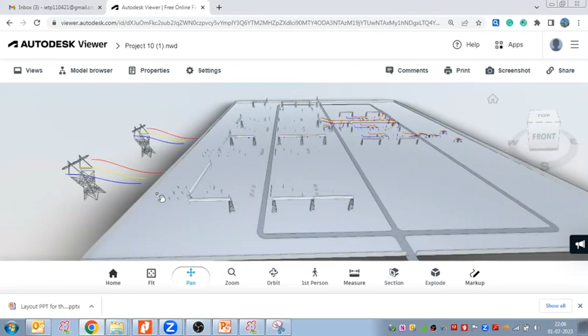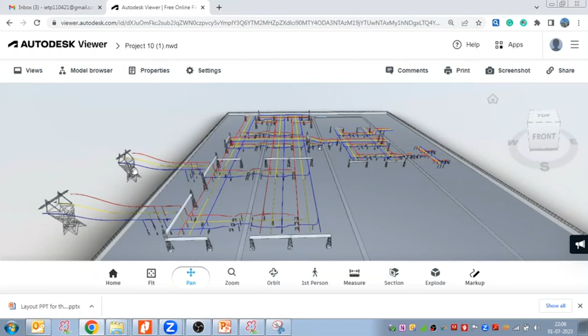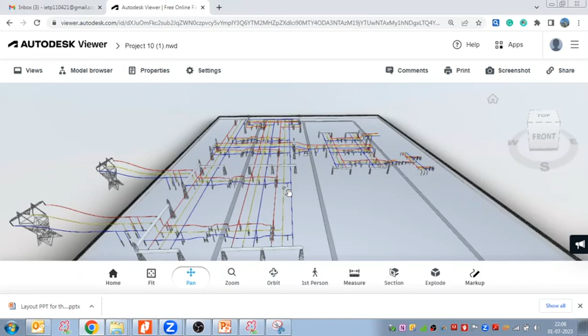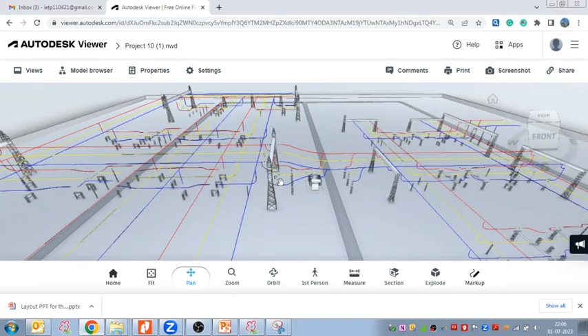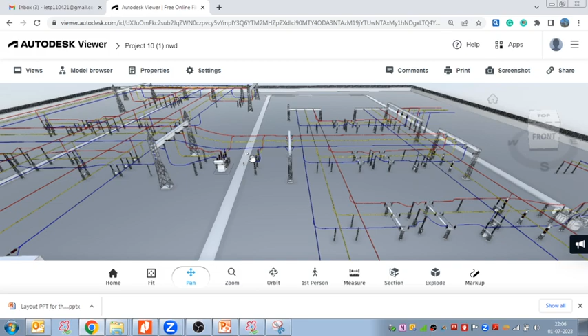So in that case the transformer should come towards the other voltage level - we can see this with an example. Here the line bay, as I told, is planned towards the incoming or outgoing dead end tower location. Once the line bay orientation is done - this is a 220 by 132 by 33 kV substation sketch. Here you see this 220 kV with the double main and transfer bus bar scheme, and we are stepping down this 220 kV voltage to 132 kV using a transformer placed over here, and now this 132 kV we have to feed to the 132 kV bus bar.